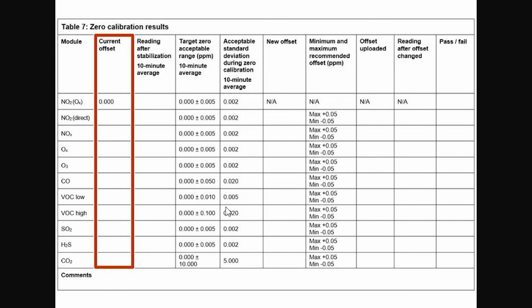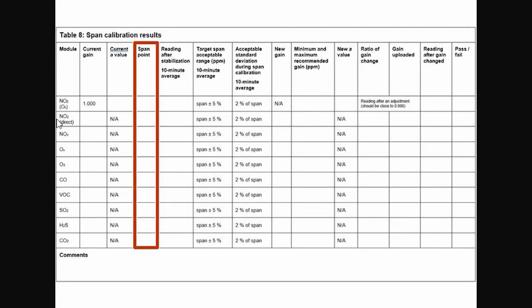Likewise for your span calibration, we were using the VOC module here, span of plus or minus 5%. We're at 20 ppm, so that number was plus or minus 1 ppm. And then we also had the standard deviation of 2% of span, so that's your tolerance there. 2% is actually 0.4, so you have quite a wide range there. It's usually even more stable than that. You don't see too much variation of those numbers in your 10 minutes of data. So okay, there you go.